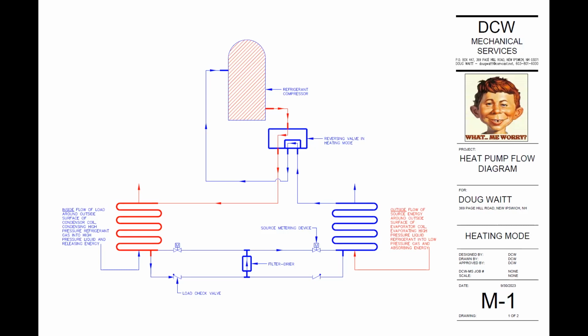The thing that makes it into a heat pump and air conditioner is this three-way valve here that changes what the two coils associated with the system do. There's a condenser coil and an evaporator coil, and they switch. When you're in the heating mode, the evaporator coil is on the outside of the building. And when you're in the cooling mode, the evaporator coil is on the inside of the building. Don't let this blow your mind. It's available for you online afterwards, but that's how a heat pump works. It basically takes energy from a source and then delivers it to the space.